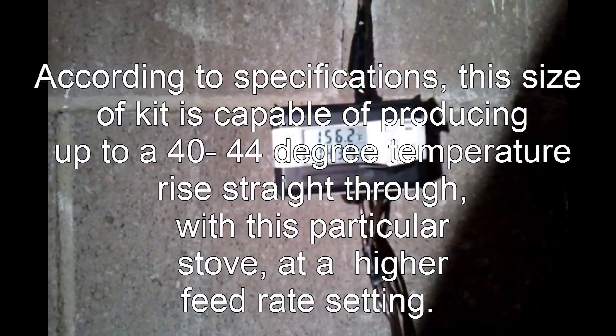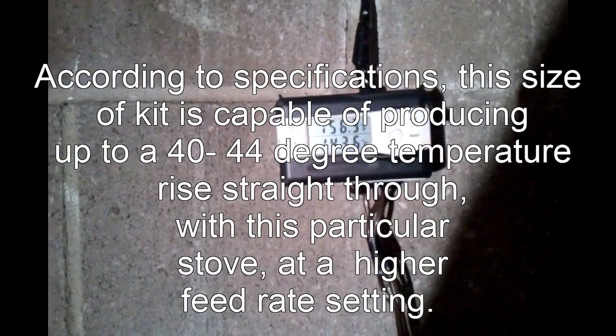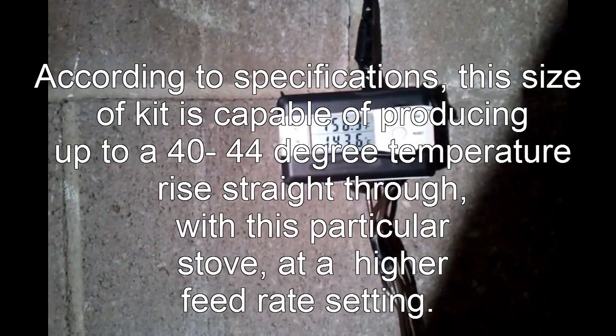This here is a display of the difference between the outgoing and the incoming water. Right now it's picking up about 12 degrees. And this will depend on the size of pump you're running. I've got a little bit bigger pump than I need on here. If this was a 007, it would probably be closer to a 17 or 18 degree difference. And I'm running at a fairly low feed rate right now. With a maximum feed rate, you can get close to a 40 degree rise through the stove. I've never had it up to that point yet.